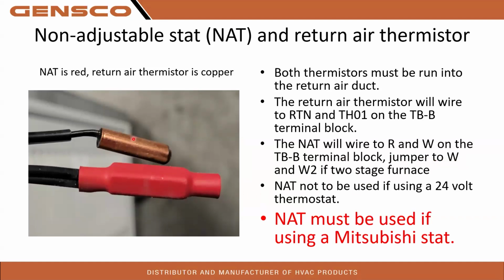Do not mix these things up on your TBB terminal block. If you mix those up, you will get a thermistor error. If you try to wire these in together on RTN and TH01, it's going to mess with the thermistor resistance value on there, and you are going to get an error. So make sure that they're separated and you're using the right one. Copper one's return air, red one's your non-adjustable stat.